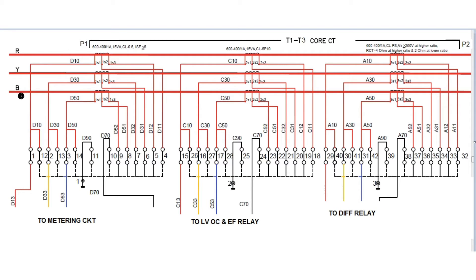Red, yellow, and blue phase is the HV side. This can be either a feeder or the LV side of the transformer if it is a 33/11kV transformer. Here the LV side of the transformer has been shown, where three cores exist for a CT. P1 is connected towards the bus side and P2 is connected towards the line side or transformer side for the transformer switchgear panel.